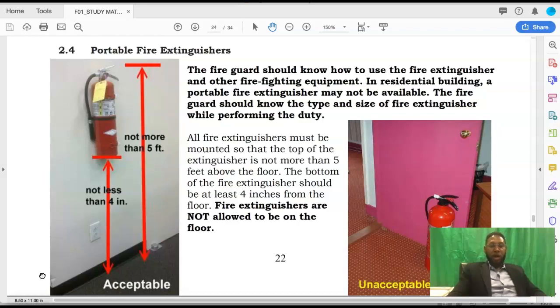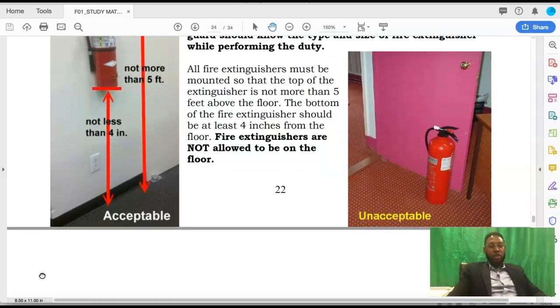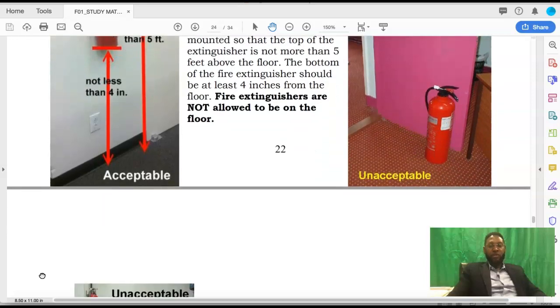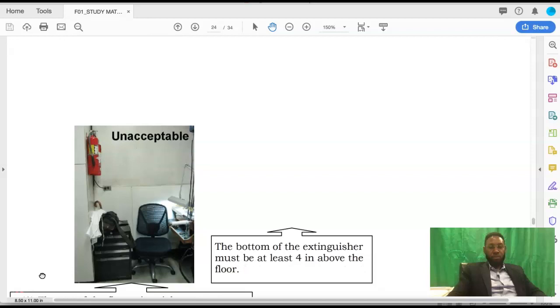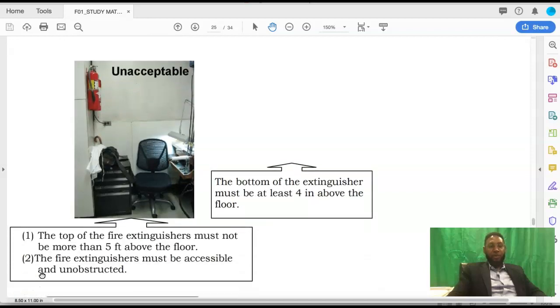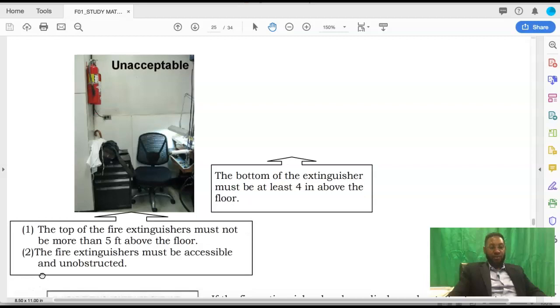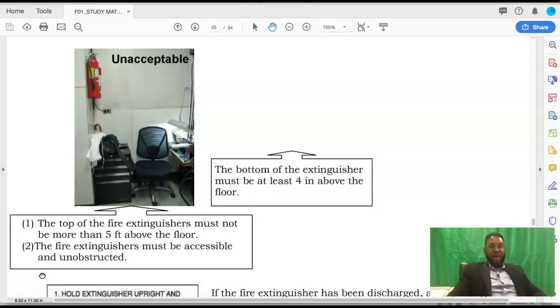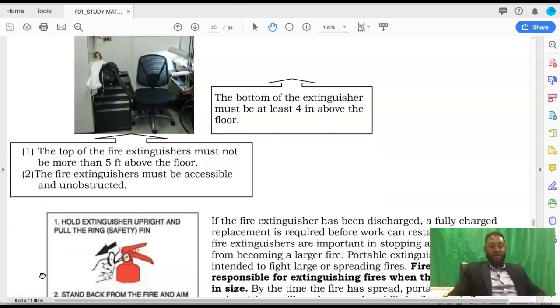All fire extinguishers must be mounted so that the top of the extinguisher is not more than 5 feet above the floor. The bottom of the fire extinguisher should be at least 4 inches from the floor, and that is the law. No fire extinguisher should be laid on the floor. It's unacceptable. Also, it's unacceptable to block access to a fire extinguisher. Alright, you can find this diagram on your page 25.